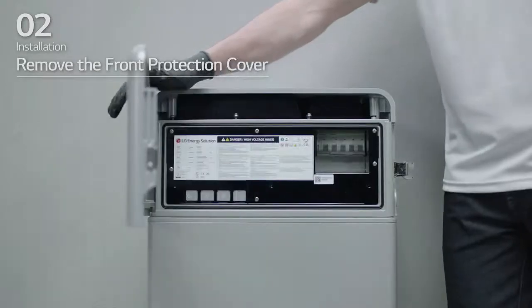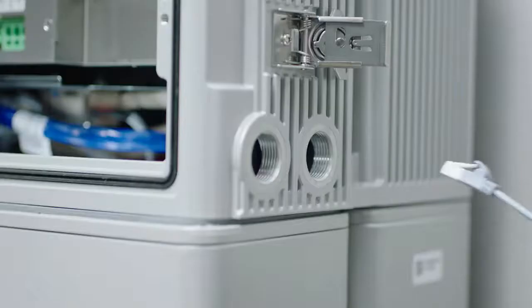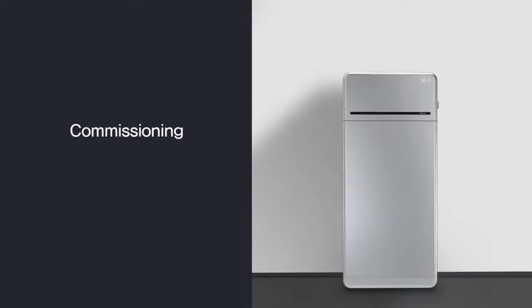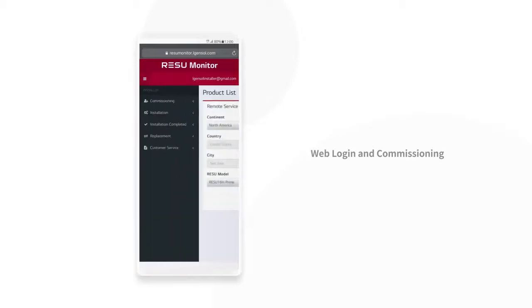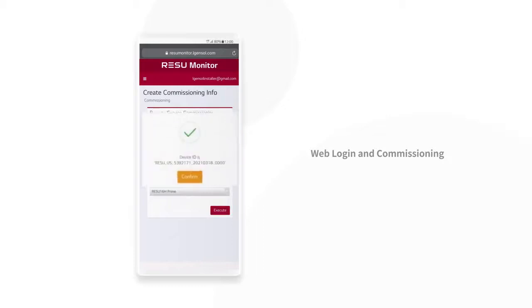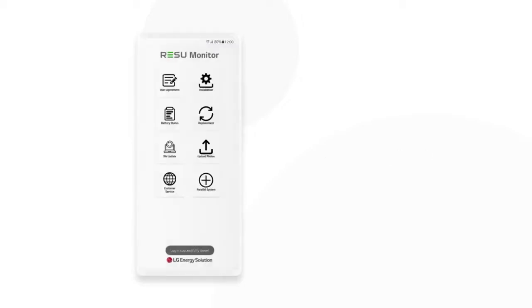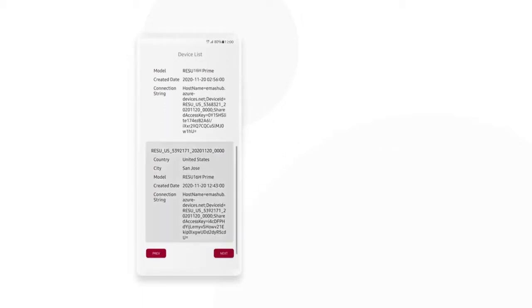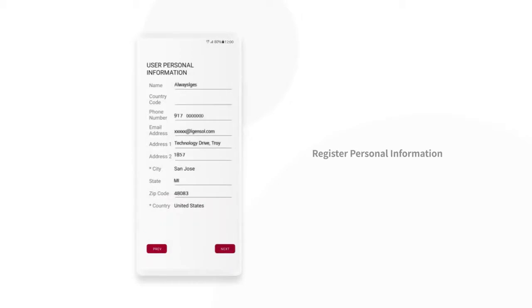Open the front cover and loosen the 6 bolts to remove the front protection cover. Insert the RMD Ethernet cable through hole number 2 and connect the cable. Then, complete the RESU Monitor setting: visit the RESU Monitor site and enter your ID and password. Access Commissioning on the left sidebar. Select Create Commissioning Info, fill in the information, and select Create.